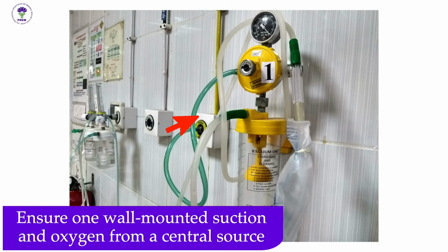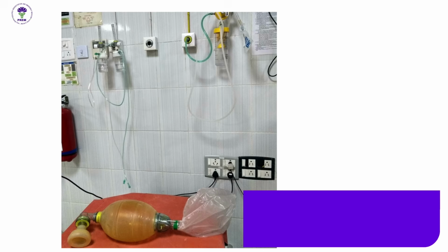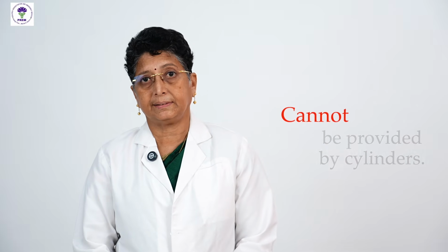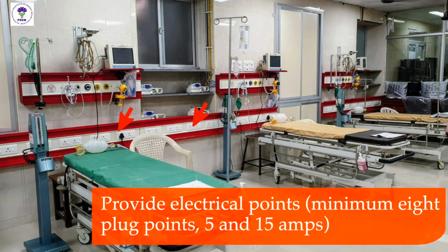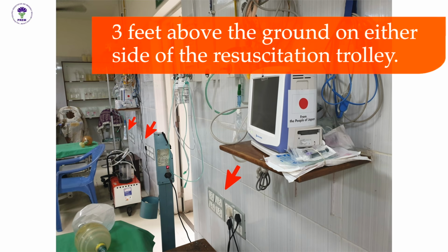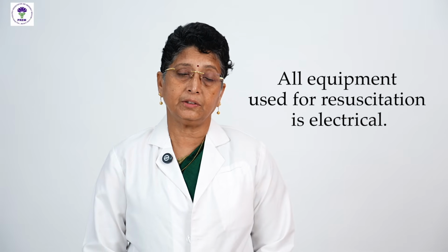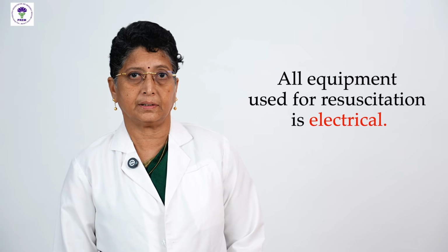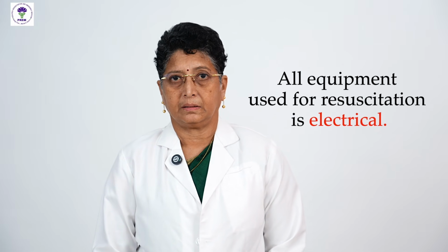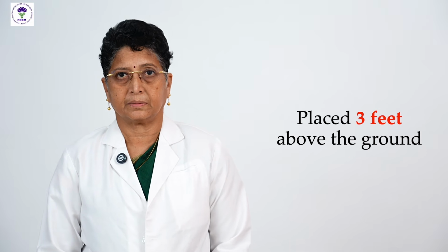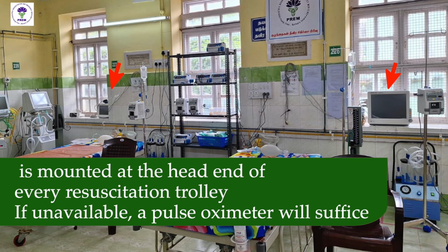Infrastructure. Ensure at least one wall-mounted suction and oxygen from a central source is available at the head end of the resuscitation trolley. Large volumes of oxygen are needed throughout resuscitation, and this cannot be provided by cylinders. Provide electrical points, minimum 8 plug points, 5 and 15 amps, 3 feet above the ground on either side of the resuscitation trolley. Virtually all instruments or equipment used for resuscitation are electrical: suction apparatus, monitors, infusion pumps. These require adequate plug points, and these have to be placed 3 feet above the ground. Make sure that a multi-channel monitor is mounted at the head end of every resuscitation trolley. If unavailable, a pulse oximeter will suffice.